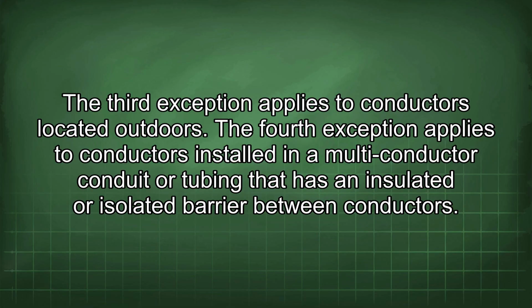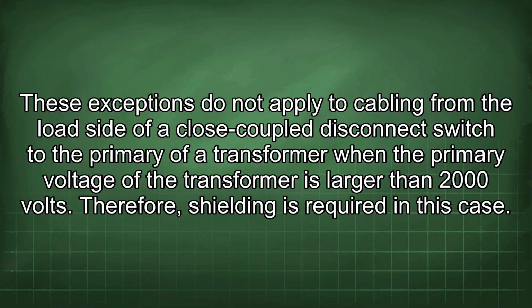between conductors. These exceptions do not apply to cabling from the load side of a close-coupled disconnect switch to the primary of a transformer when the primary voltage of the transformer is larger than 2000 volts. Therefore, shielding is required in this case.